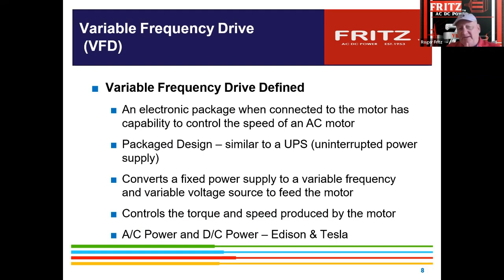So variable frequency drive, defined basically, is an electronic package that, when connected to a motor, is capable of controlling the speed and power to that motor. They're a package design. Some people don't realize an uninterruptible power supply is basically a hybrid VFD. It's just fixed frequency output, but they're able to regulate and make sure that power is steady. And then they sometimes use DC batteries on the DC bus circuit to regulate. So even if the power is fluctuating out there, it always has the DC to still build the output correctly.